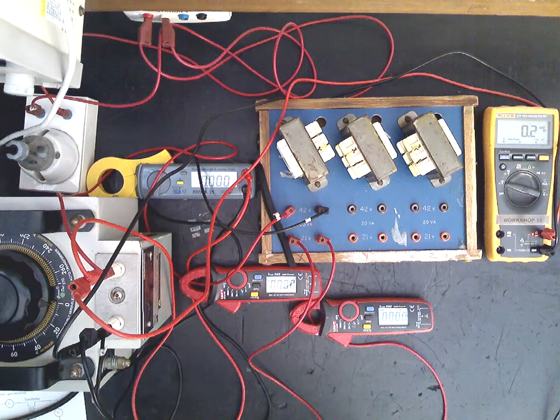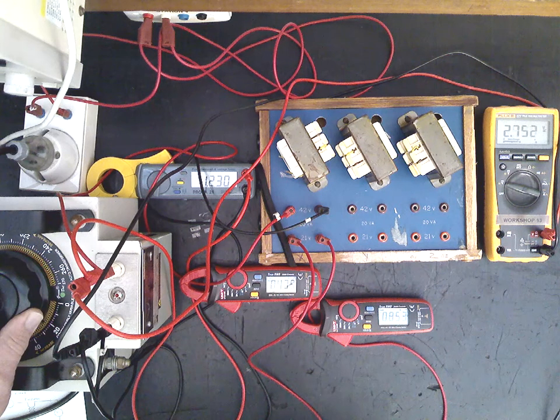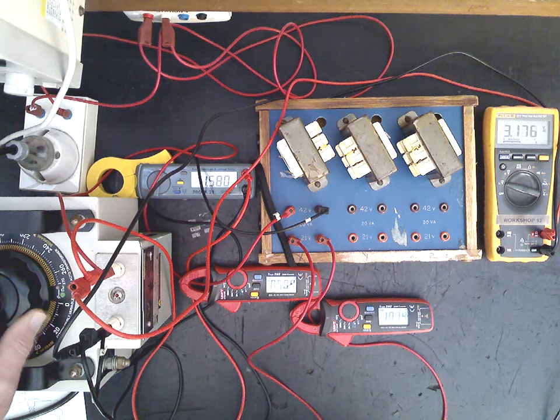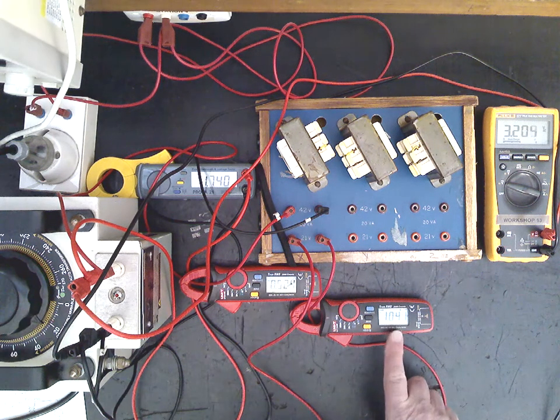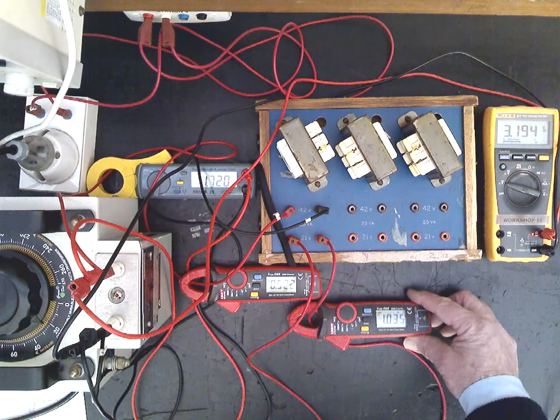turn the power supply on, and then wind slowly up your variac until you're achieving full load current in the secondary of the transformer. We're seeing there about one amp flowing through there.